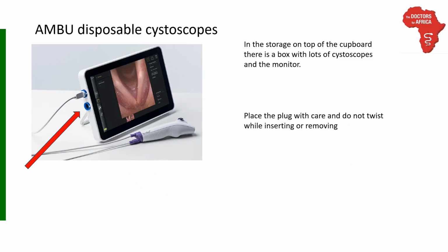The telepack light source monitor camera doesn't need much explanation. In the storage in Accra, on the top of the right cupboard, there is a box with many disposable Ambu flexible cystoscopes. There's also a monitor. The scopes can be used about 5 to 6 times before the image gets disturbed. Then discard them. For sterilization, put them in the PeriSafe fluid up to where the irrigation opening is in the fluid too. Irrigate this opening with a syringe with the PeriSafe solution. The tiny gold-colored contacts in the plug are very vulnerable. Place the plug with care and do not twist while inserting or removing.